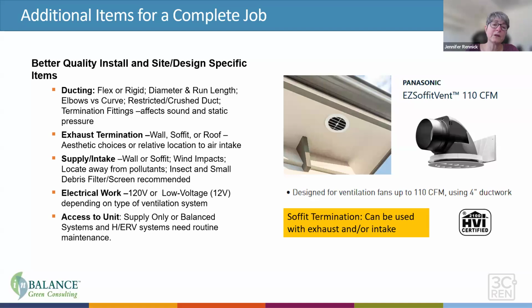And then some of the other stuff to really consider when you're looking at these systems for the actual installation is whether the ducting is going to be flex or rigid. I mean, as architects, you don't have too much control over this, but you can go to the job site and you can talk to people and find out what's going on. So for example, restricted or crushed ducting is not going to work well. Plus, it greatly affects the sound that your clients hear and the static pressure, which makes the units work harder if there's too much static pressure.